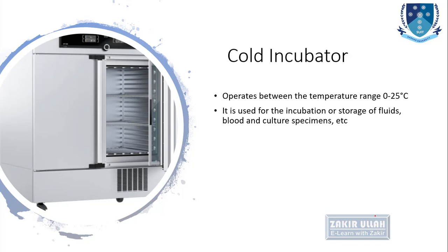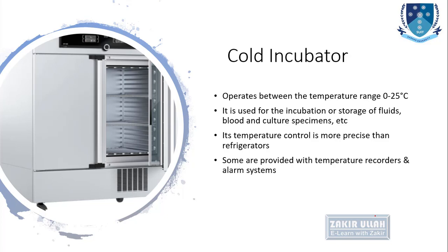So they are incubated in a cold type of incubator, and its temperature control is more precise than a normal refrigerator. That's why they are called cold incubators, because the sensors and instruments installed in them are more precise than a routine refrigerator used at home or in the laboratory.